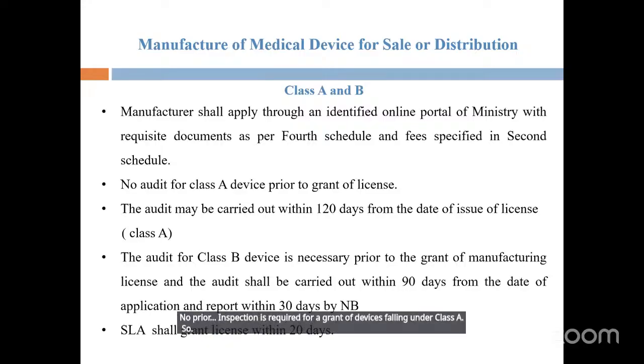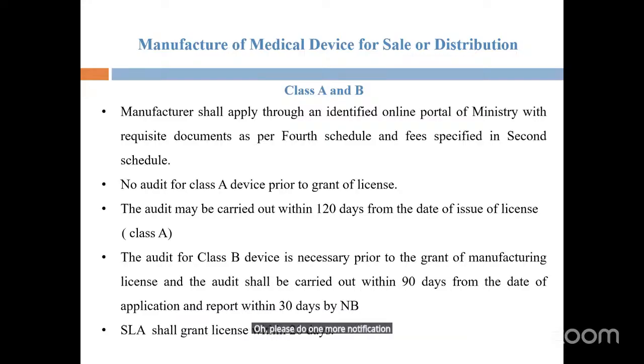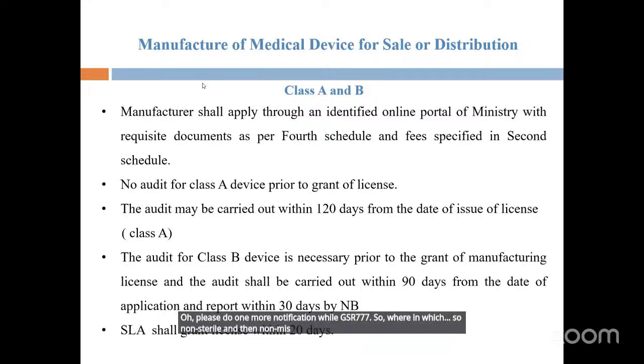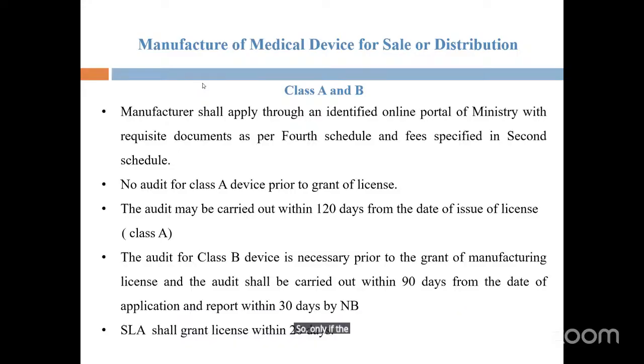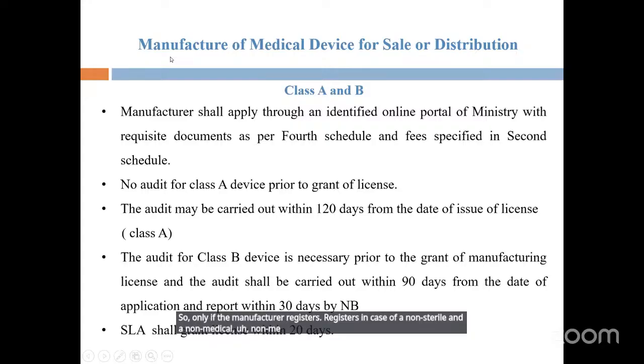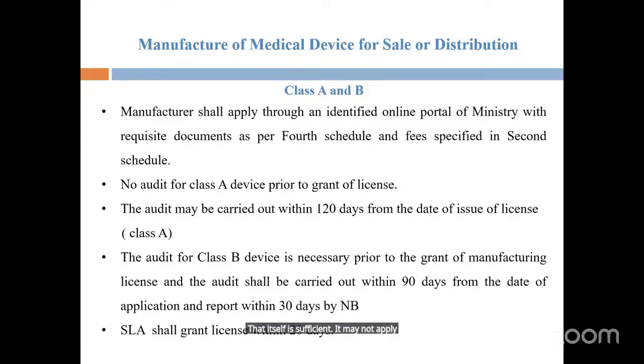Further to that, the Government of India has published one more notification, vide GSR 777, wherein for non-sterile and non-measuring devices there is no requirement of a medical device license. Only if the manufacturer registers in the case of non-sterile, non-measuring devices, that itself is sufficient. You need not apply for a license.